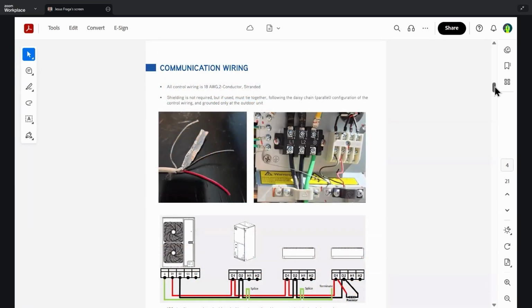So the communication wire, nothing really changes on this side of it. We're still going to run our 18.2 from the outdoor unit. It's going to be D1 and D2 in the ground. So we know that we have D1 and D2 from the outdoor unit goes to the first indoor unit. From the first indoor unit, goes to the second indoor unit, and so on and so forth. And the last unit in line is going to receive the quarter watt, 120 ohm resistor that comes with the outdoor unit. And so what you can do is place that across D1 and D2. That way you don't have any type of communication errors or communication faults when the system actually starts up.